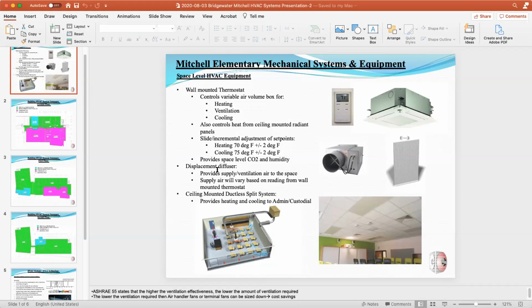This nicely filtered ventilation air will come into contact with the occupants - students, teachers, staff - and then rise upward. So contrary to your normal overhead distribution, which mixes the entire room volume, with the displacement system we're displacing and moving the air upwards, removing pollutants rather than mixing them within the space. So it's highly effective for pollutant removal.